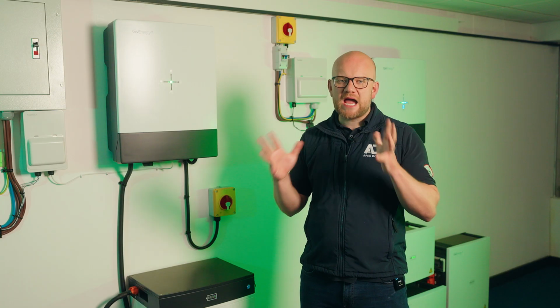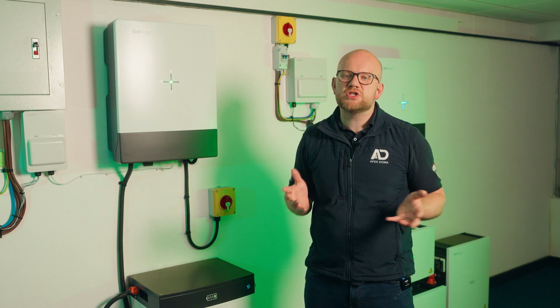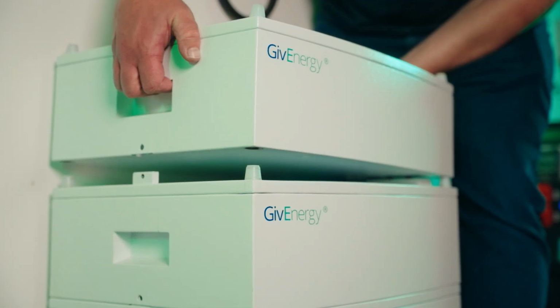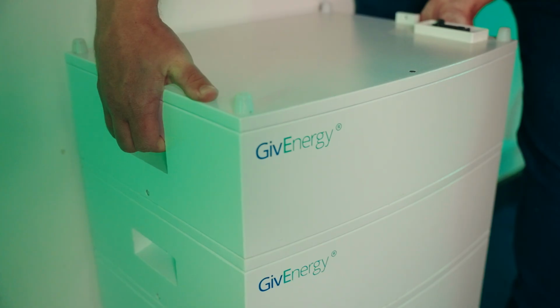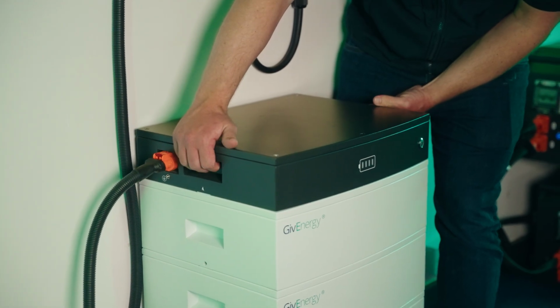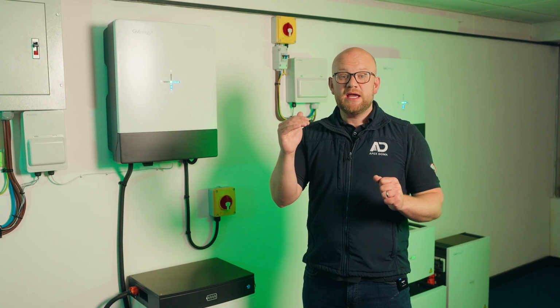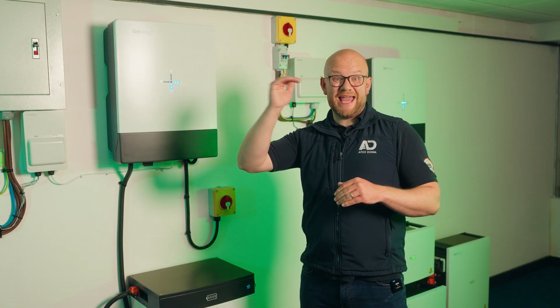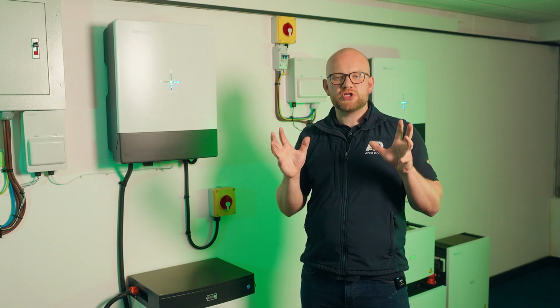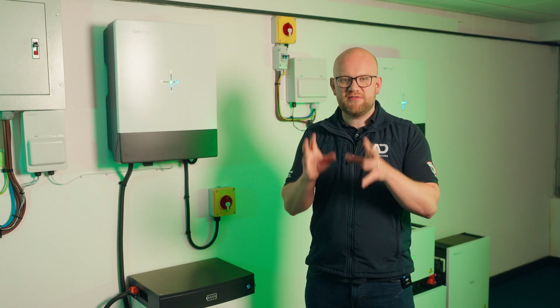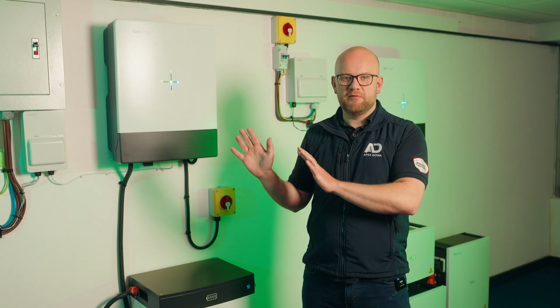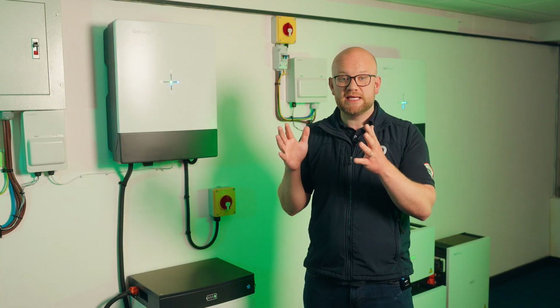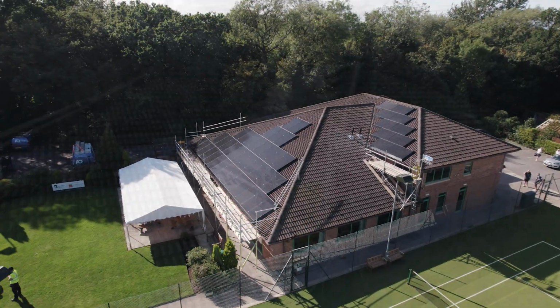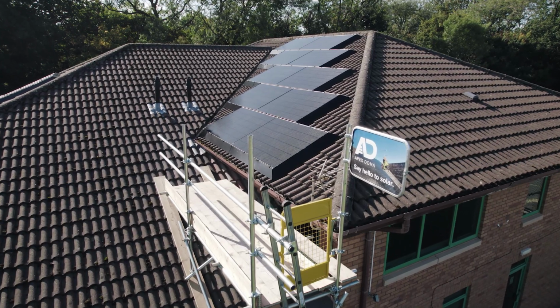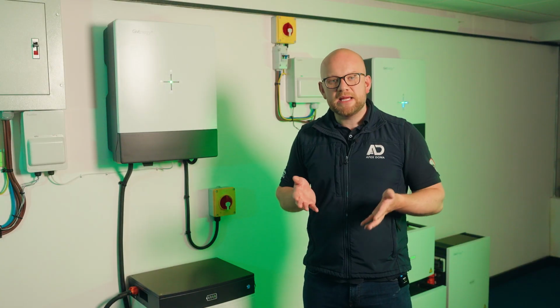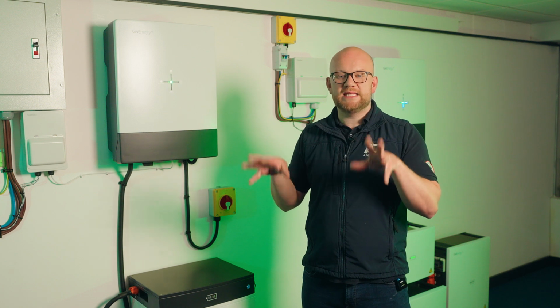Something to note about the high voltage single phase and 3-phase versions is the fact that the number of battery stacks dictates the amount of charge and discharge that you can get from your overall system. So the limit of a single phase inverter would either be 8 or 10 kilowatts. Now in both scenarios, the battery stack doesn't affect the solar input. So if you have 10 kilowatts worth of solar generating, the number of battery packs won't limit the amount of solar you can convert using that inverter. However, what can be limited is by the number of battery stacks you have.